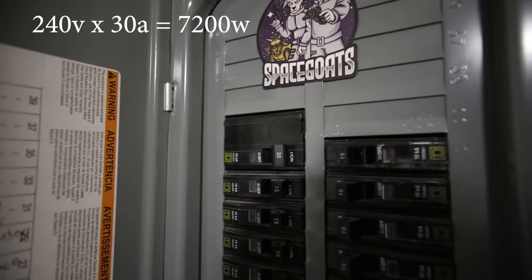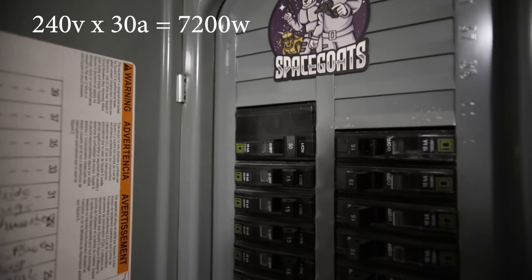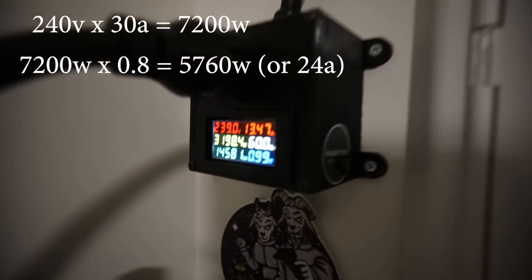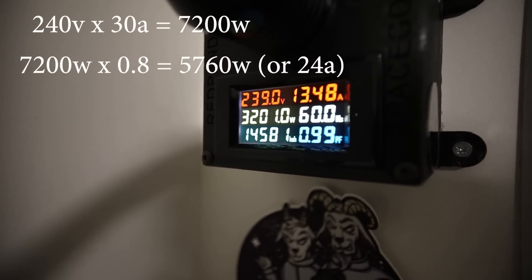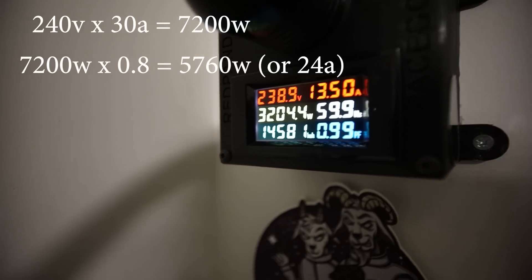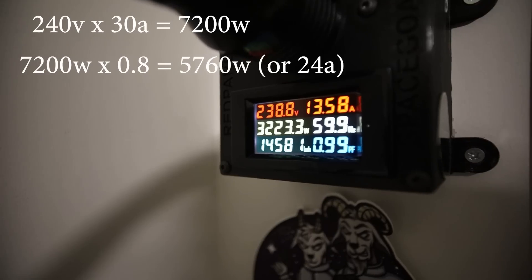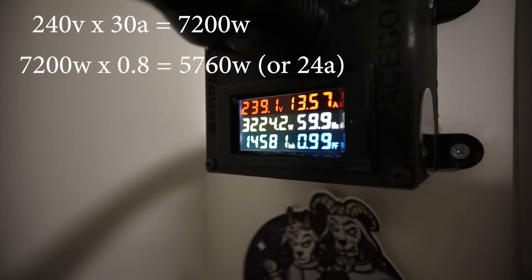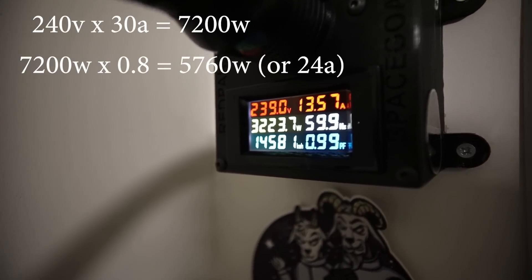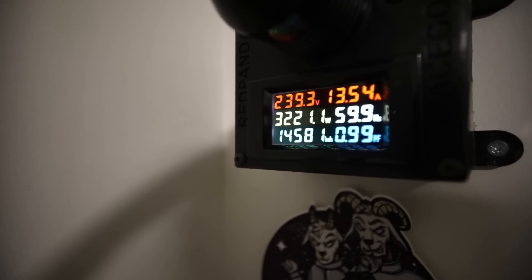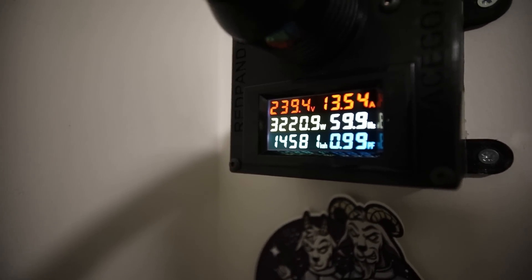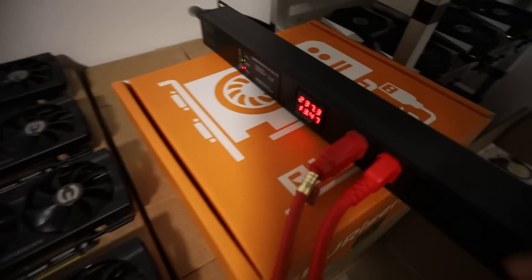Now, we are wanting to do the 80% rule. And so we want to make sure we don't go up past 24 amps or 5,760 watts at 240. We want to make sure we stay around that 80% rule just for safety and all that kind of stuff. We want to be mindful of that. So we are under that 5,760 watt capacity 80% rule. So we're at 3,200 right now on a single S19J.